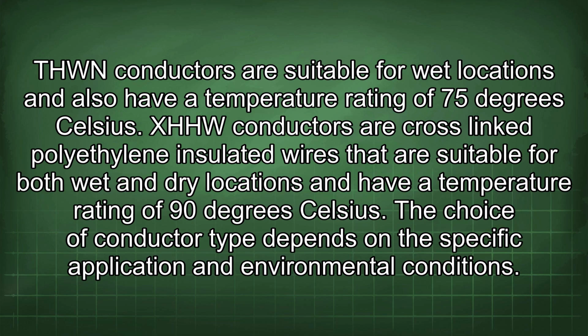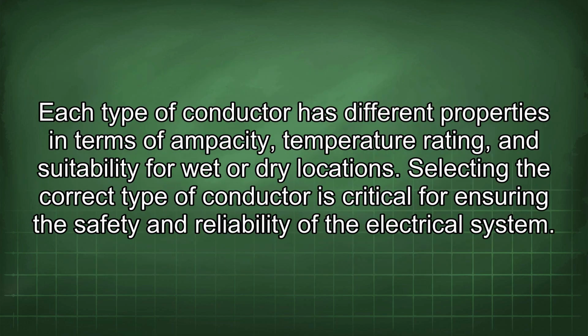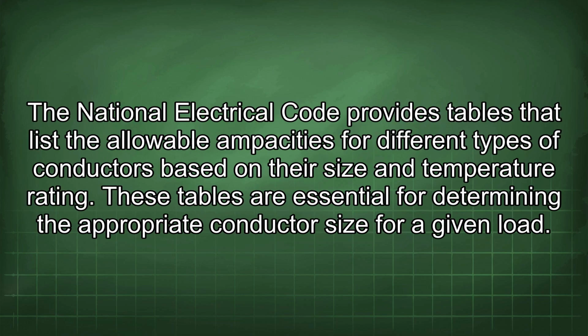The choice of conductor type depends on the specific application and environmental conditions. Each type of conductor has different properties in terms of ampacity, temperature rating, and suitability for wet or dry locations. Selecting the correct type of conductor is critical for ensuring the safety and reliability of the electrical system. The National Electrical Code provides tables that list the allowable ampacities for different types of conductors based on their size and temperature rating.